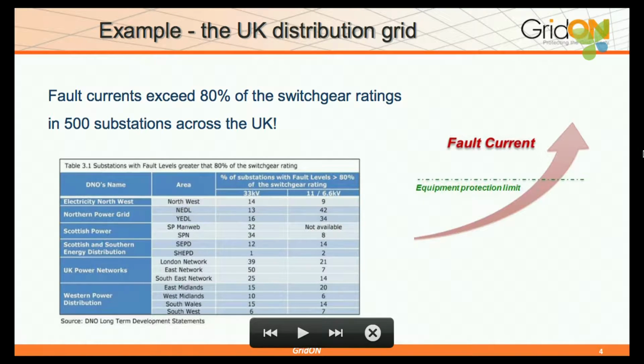Here is an example from the UK market specifically. It's a study published by Western Power Distribution, showing that already 500 substations in the UK, the fault level, or the prospective fault level, is exceeding 80% of the equipment protection capability. And this is where it starts to get risky, when you're going above the protection capability.